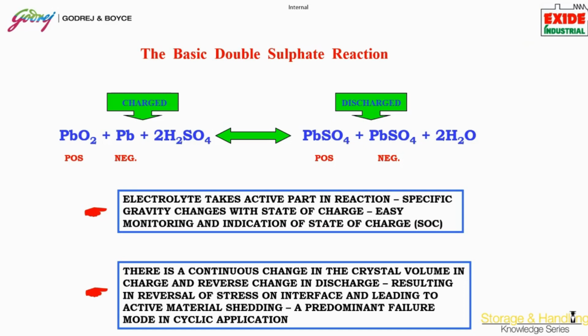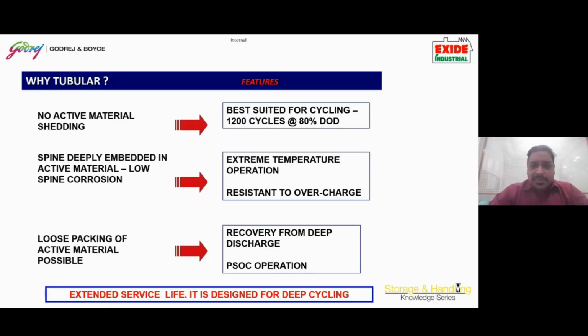You might be asking why tubular batteries only in traction batteries. The answer is, there is no active material shedding in tubular batteries, and the spines are deeply embedded. These batteries can survive extreme operational conditions like temperature and humidity, and they can run over 1,200 cycles at 80% DOD. One charge discharge, when a battery is discharged to 80% depth of discharge and recharged again, is one cycle.